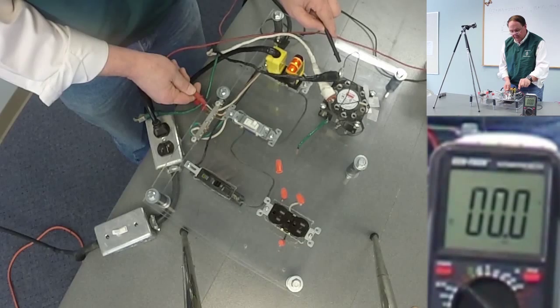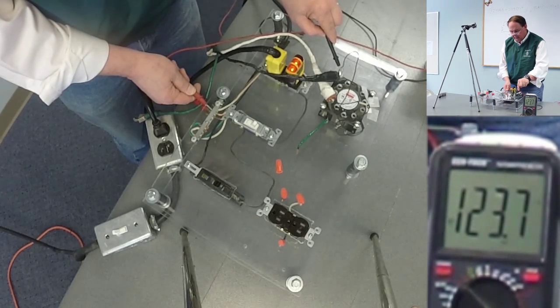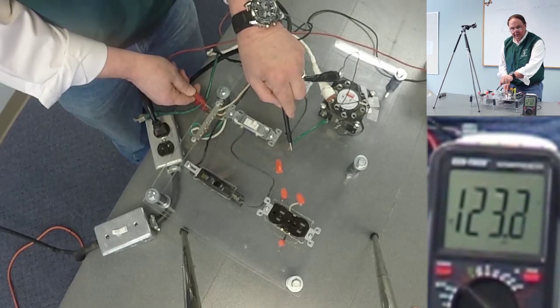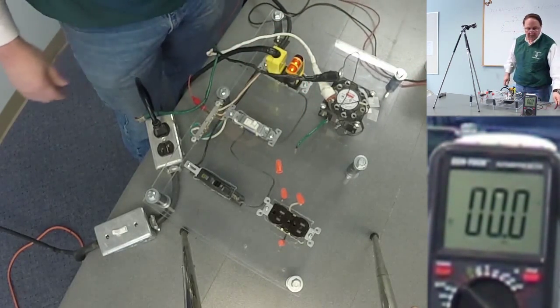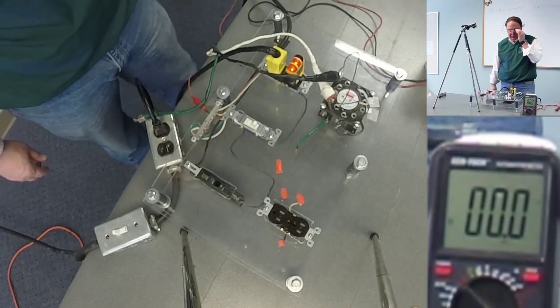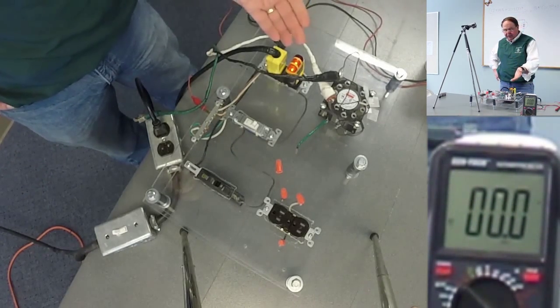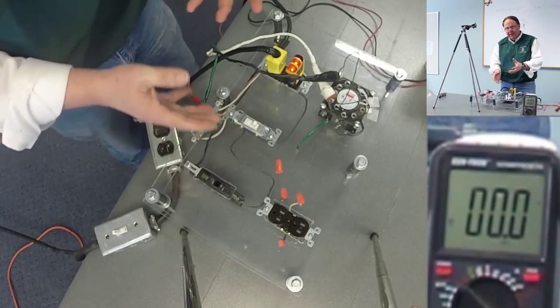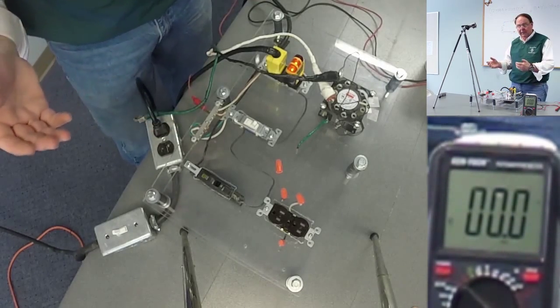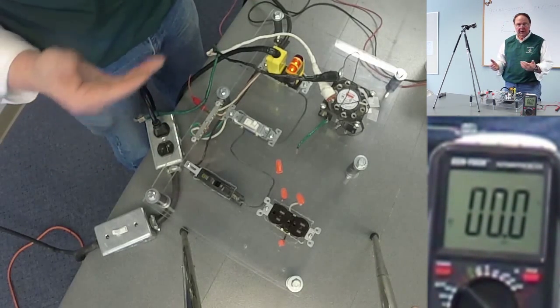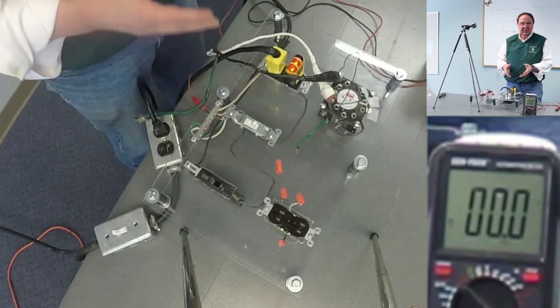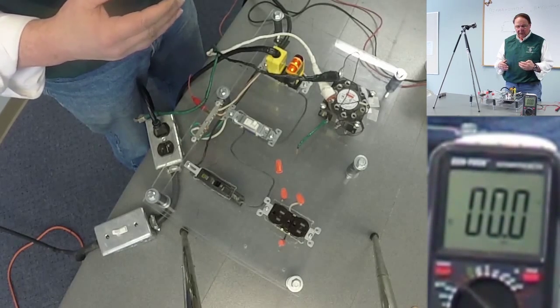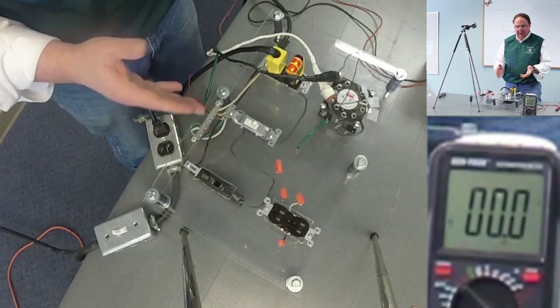If we take the tester and go from the grounding bus to the ground terminal, you should see voltage there. It's going to be probably approximately 120 volts around that area. So this is energized. I don't want to touch it. A lot of folks will tell me, especially when they improperly ground the system, 'What's the problem? The system's working.' Well, working is not a good indication. Just because this system is running doesn't mean it can't kill you, because it can.